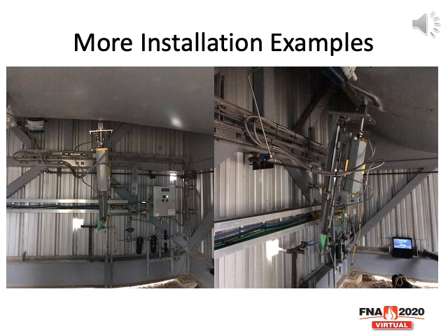But the mounting of the camera to the furnace is an important thing to consider when you're evaluating this technology. You know, where can I put the infrared camera to get the best view of the product inside the furnace? So that's usually the first consideration. And then secondarily, you'll think about just practical things such as space outside the furnace. You're going to need at least 6 feet of space just for the camera system to move and retract and just to install and work on it.